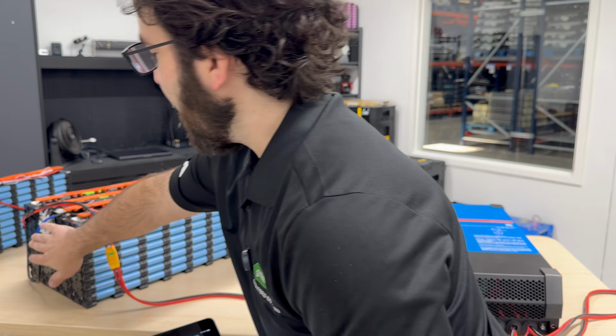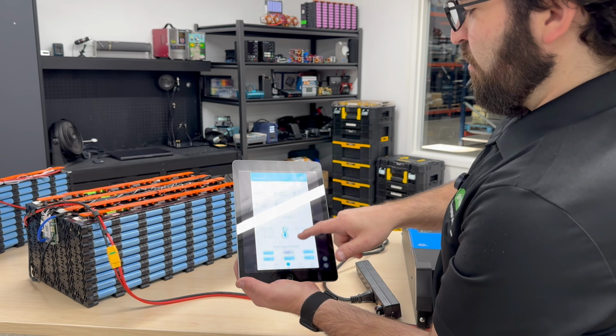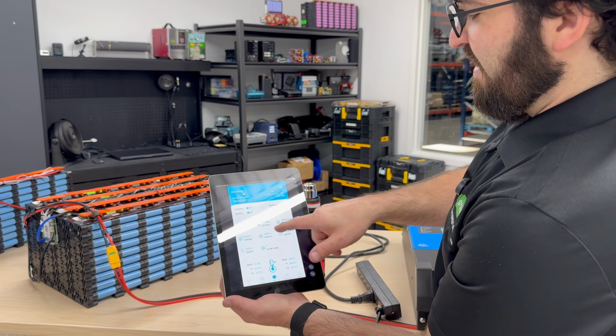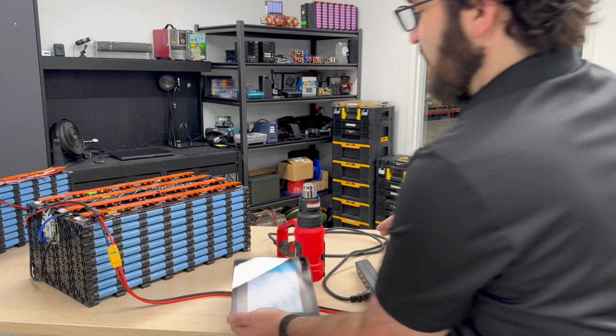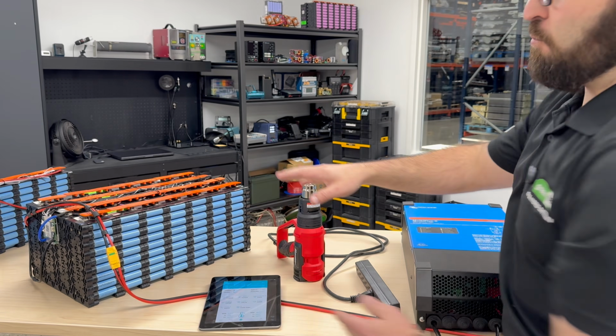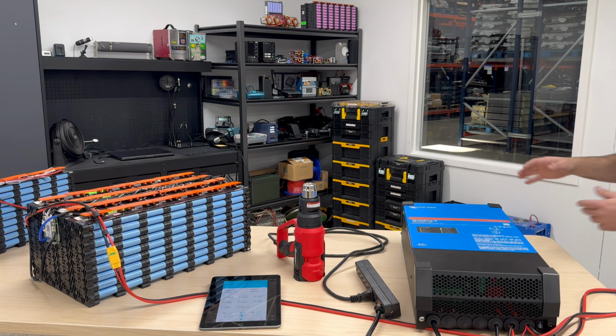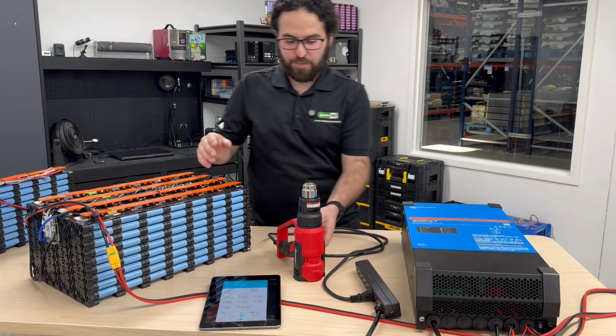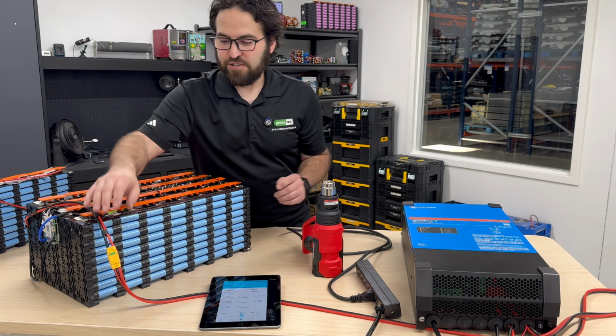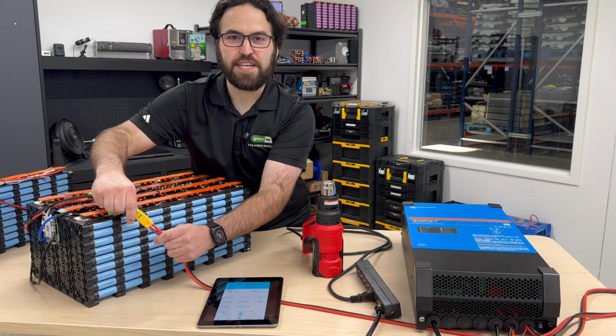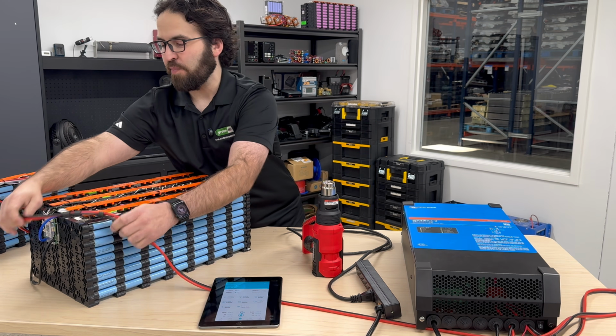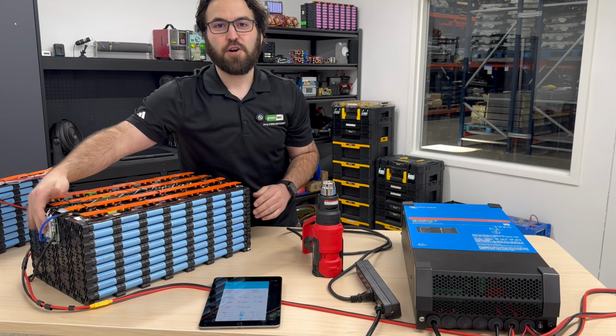So 74 degrees on the batteries and 88 on the BMS are super low. This BMS can handle 50 amps and it's only running at 18 right now. Even at 50 amps it wouldn't get more than, I'd say, 20 degrees warmer than room temperature. So these silicone wires are never going to heat up, and these plugs aren't ever going to heat up with a 50 amp continuous or 100 amp peak BMS.